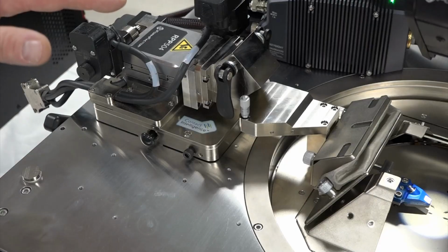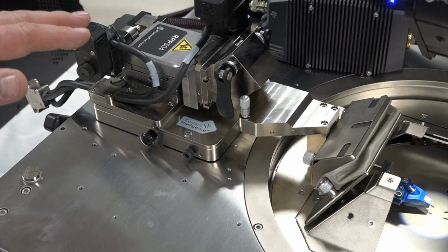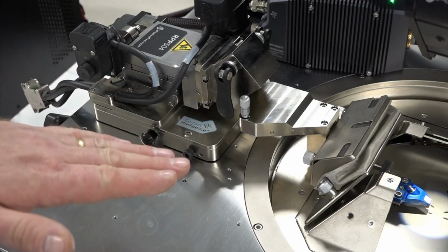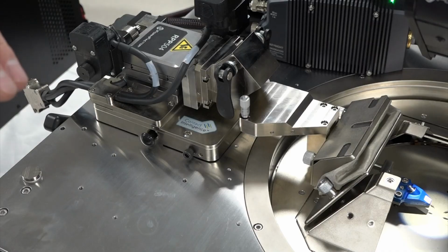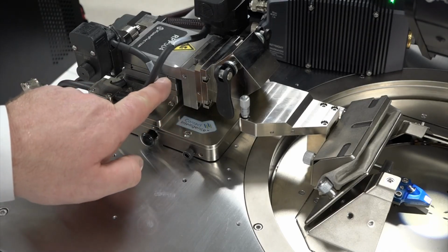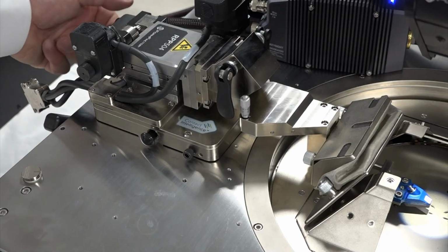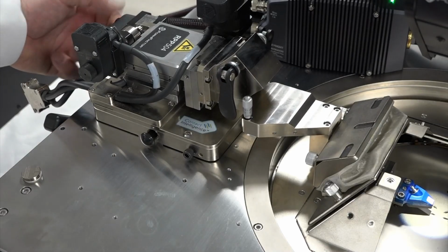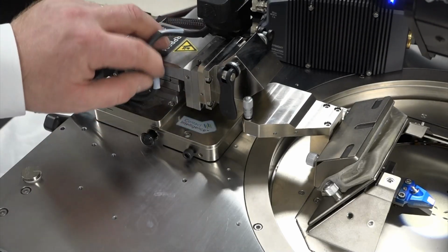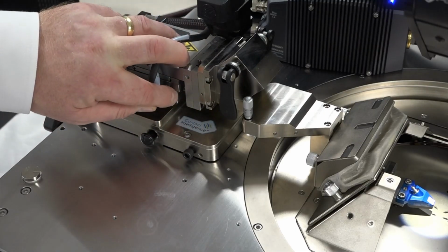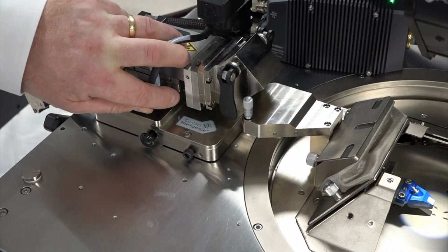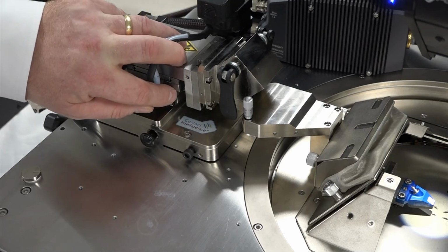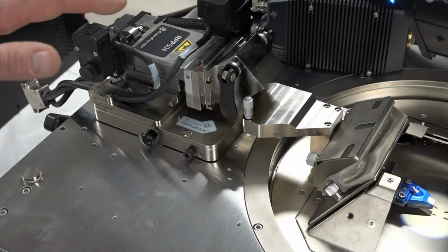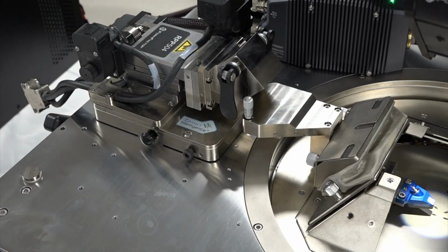So if you have a long transmission line, you might have the situation that if you were trying to move one probe backwards to reach the end of the transmission line, you might have some difficulties. So what I tend to do is bias the position about halfway forwards. Not all the way, just about halfway forwards. So around there, there's approximately 3 millimeters between the leading edge and the position. I don't want anything to be too stretched. I don't want to be reaching the end of travel.